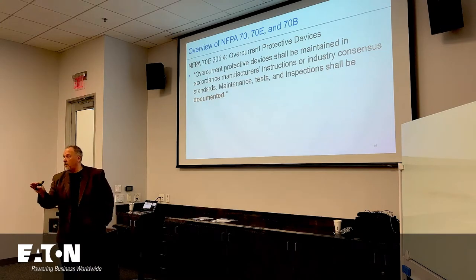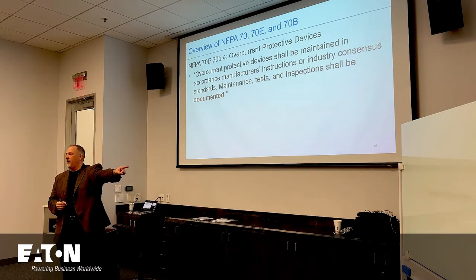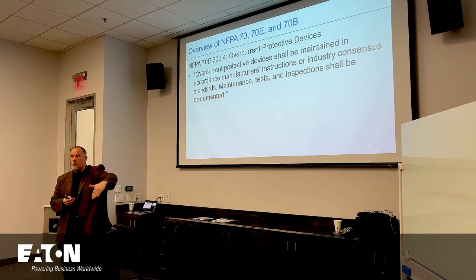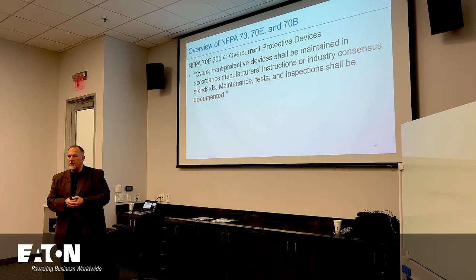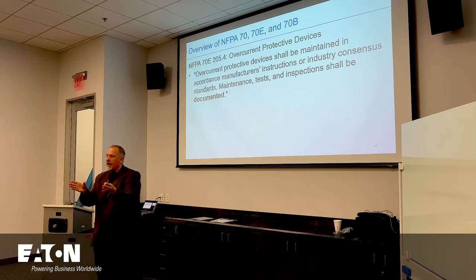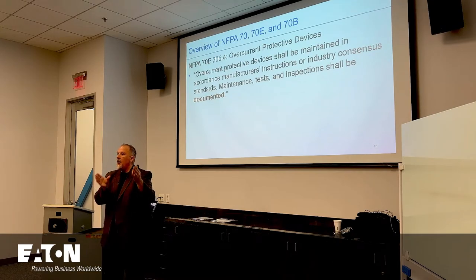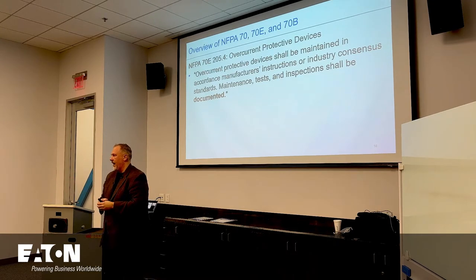There are a lot of tools for you though. If your maintenance says you have to cycle a circuit breaker annually, and you have a communication system to that piece of that circuit breaker, and you're logging when it's opened and closed, you probably will be able to say, look, that thing was opened last week, and I don't have to do that. So you can strategically plan your maintenance in your facility the more data and information that you have.